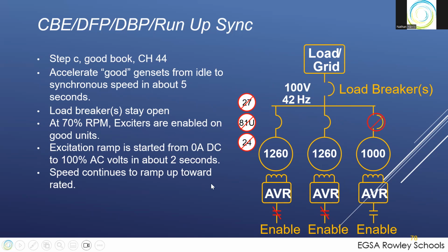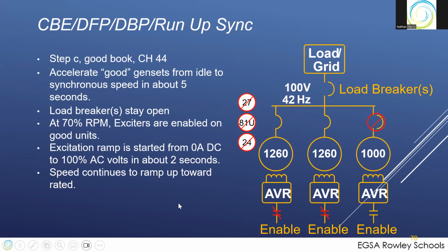The ramp is started, and I say this carefully, from 0 amps DC, from no excitation current, to 100% AC volts. And I say that very carefully. It doesn't take much excitation current, maybe 10%, to achieve rated voltage with no load. Remember we talked about that yesterday? So you can actually start up and bring it up to 100% voltage.